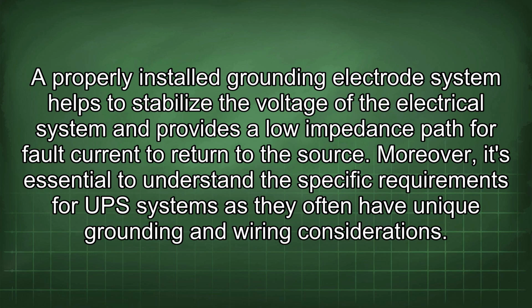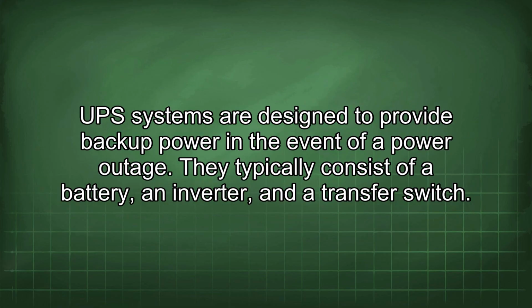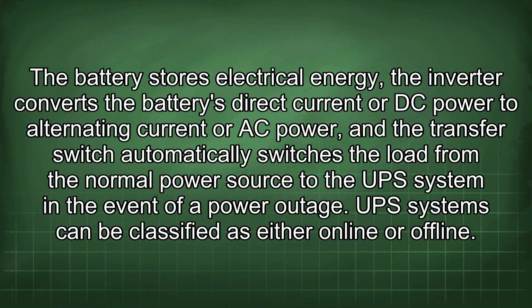Moreover, it's essential to understand the specific requirements for UPS systems, as they often have unique grounding and wiring considerations. UPS systems are designed to provide backup power in the event of a power outage. They typically consist of a battery, an inverter, and a transfer switch. The battery stores electrical energy, the inverter converts the battery's direct current or DC power to alternating current or AC power, and the transfer switch automatically switches the load from the normal power source to the UPS system in the event of a power outage.